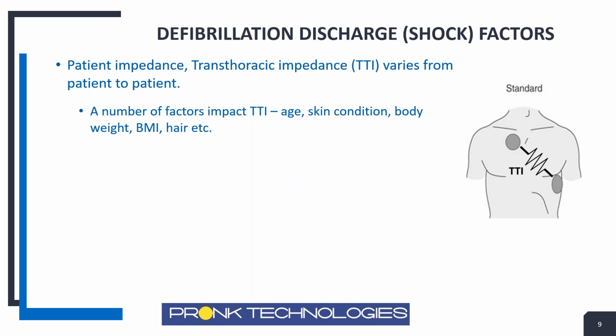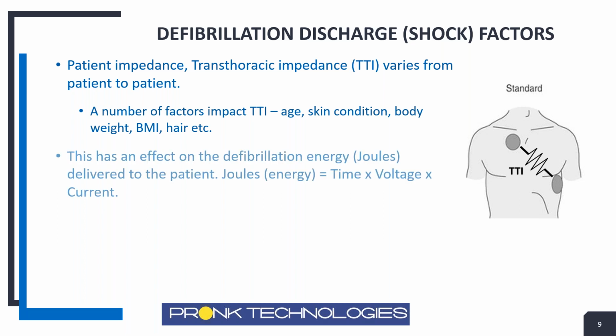So of course, for defibrillators, you're attaching the paddles or you're attaching the disposable pads to the patient, and it has a resistance between the 2 points. And this resistance varies, and that's what they refer to as a TTI value. It varies depending on the person's age, their skin condition, their body weight, their body mass index, their BMI, how much hair is on the patient, oils, etc. So these things cause that impedance to be different depending on the person. And so this can impact how the defibrillator delivers its energy.